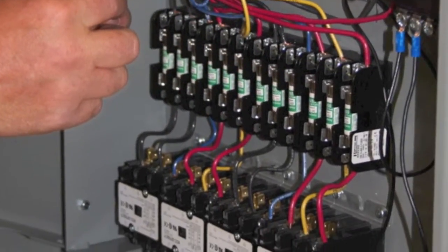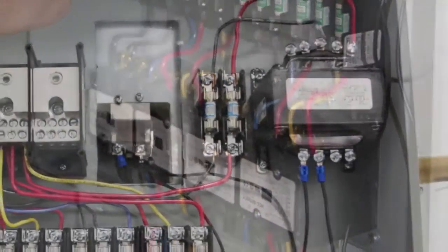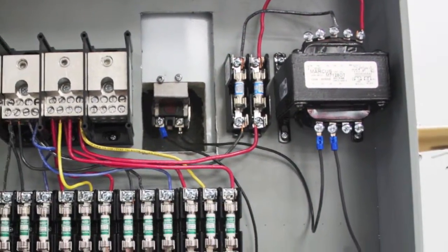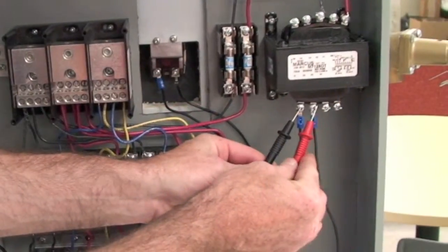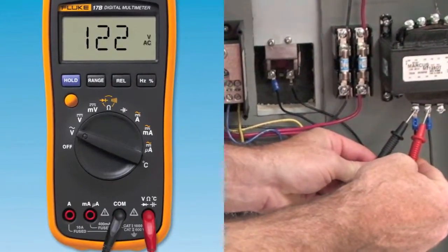The input voltage designations selected on transformer should match actual measured incoming voltage. Verify output load side of transformer by measuring 120 volts AC across terminal designations X2 and X1.